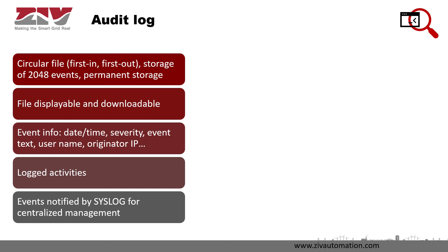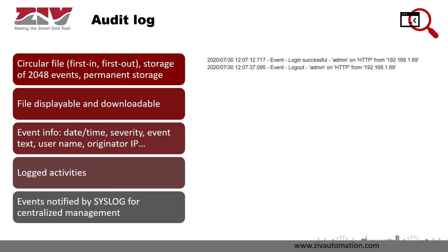There's no way to remove the audit log. This file is displayed on the web page of the IED and can be downloaded through the web page, file transfer, or IEC 61850. Each event includes information like the date and time of occurrence, the severity, whether it's an event or an alarm, the event text description, the username, the originator IP address, etc. Here's an example of a successful login and logout of the user admin over HTTP from a given IP address.